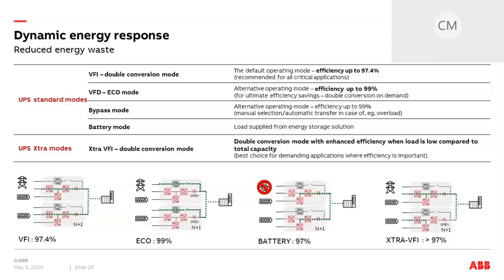But how do we achieve such high efficiencies inside the system? This is because we optimize the power consumption of the UPS, and then we are able to reduce and minimize the energy waste according to the operating mode. Our target is providing continuous uptime with the best efficiency, with a view of load considering on-site conditions. Therefore, we have implemented different operating modes in our UPS, such as VFI or double conversion mode. In this case, the IT load is granted the best power quality.